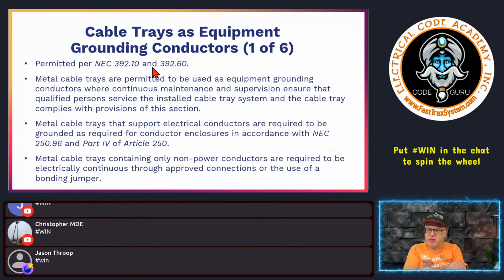However, in applications like industrial establishments, and your AHJ is going to qualify what that is, you can't just make something an industrial establishment. Typically, it's producing or manufacturing a product, not just selling a product like a Walmart. That wouldn't be an industrial establishment. If the building you're wiring is located in an industrial park, then it's typically zoned as an industrial building, and if that's the case, you could put single insulated conductors or single conductor cables in a cable tray.